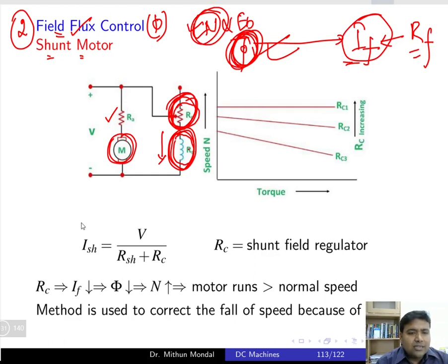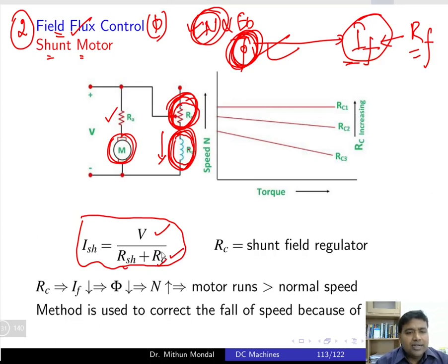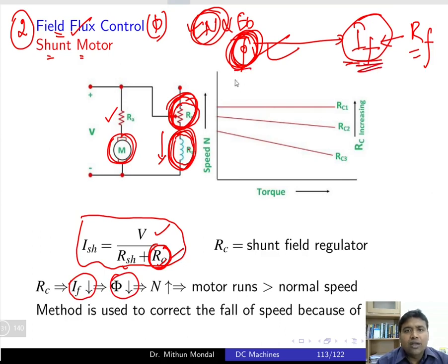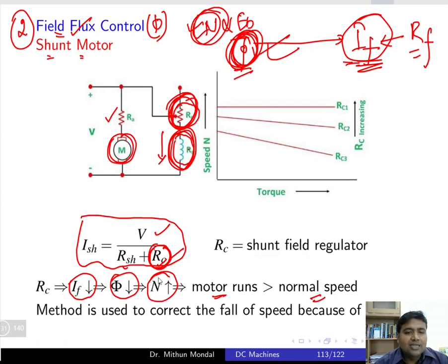The shunt field current equals the supply voltage divided by the sum of the shunt resistance plus the field rheostat resistance. If this resistance is increased by adding the rheostat, the field current falls, causing the flux to fall. When flux falls, the speed of the motor increases — the motor runs at a speed greater than the normal speed, which was not possible with the armature control method.